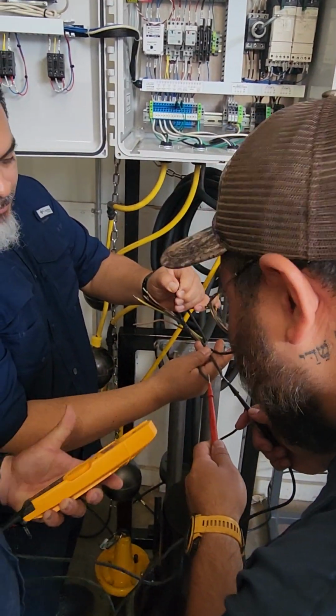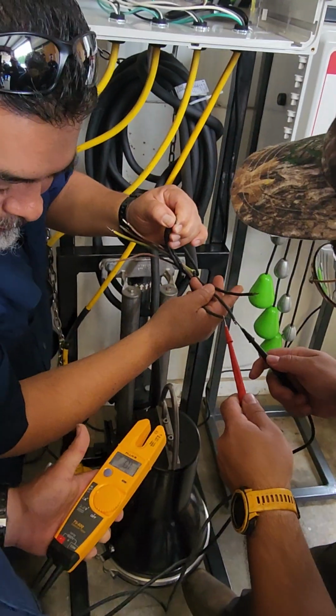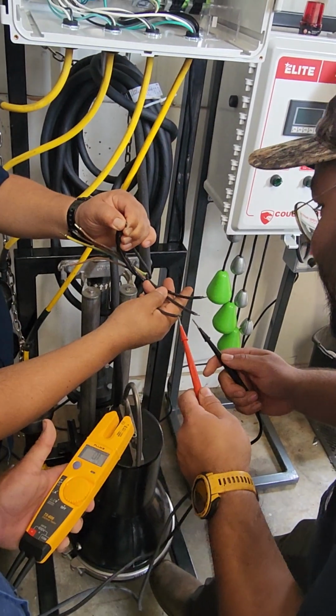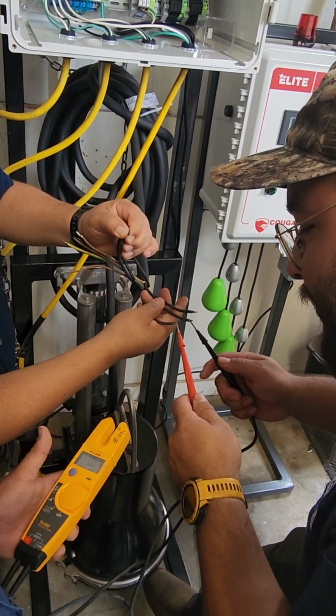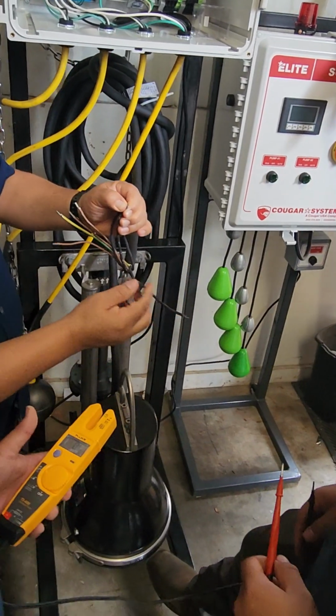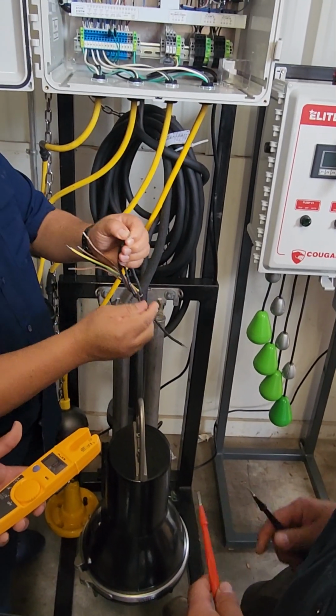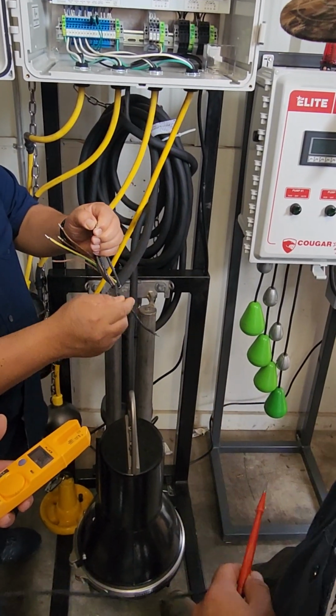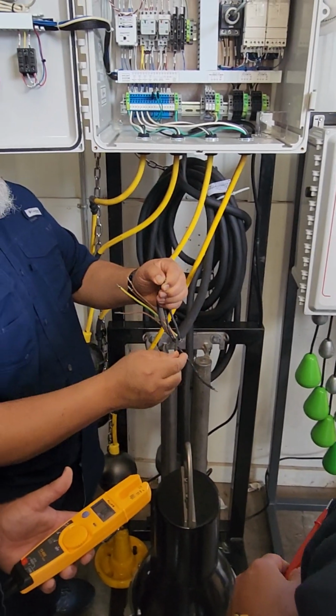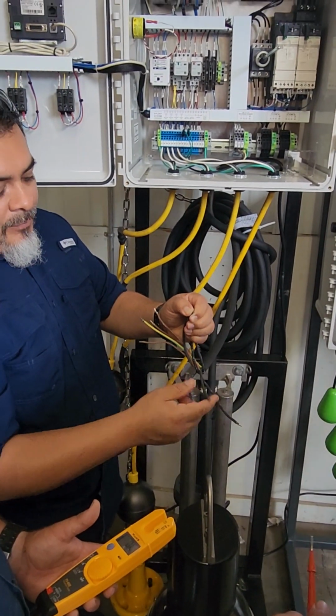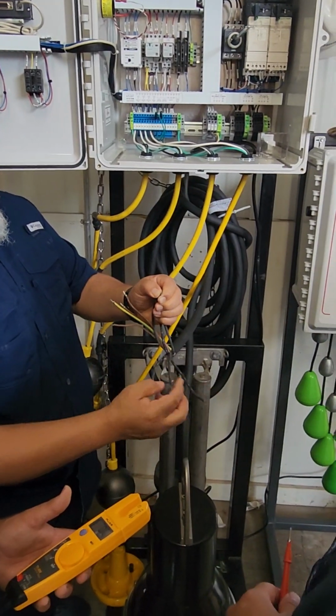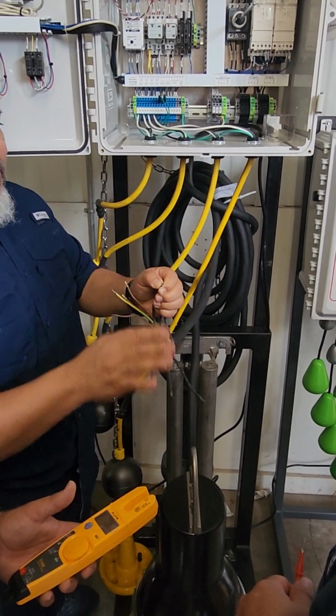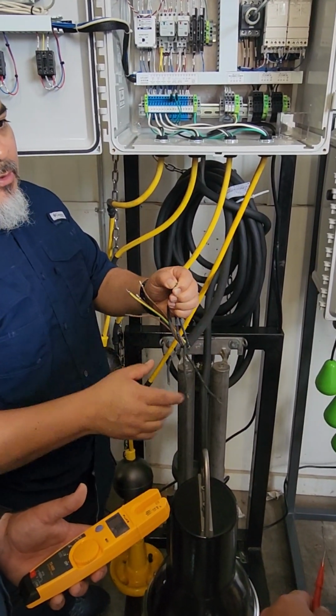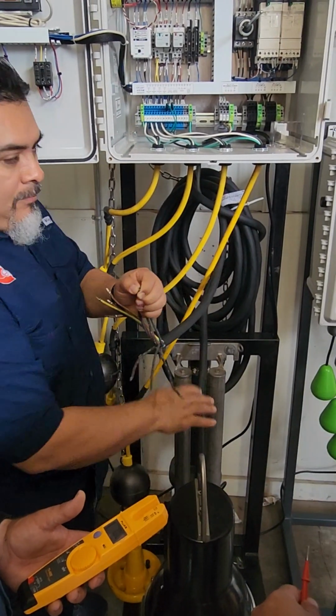This one? What I got? Nothing. You got it on ohms. 1 and 5. Okay. Normally on a 3-phase motor, when you check between the leads on ohms, you'll get either a 1.5 or 3.5. So you check all 3, 1 and 2, 2 and 3, and all of that, and you should get the same number on all leads. That's indicating the motor's good.